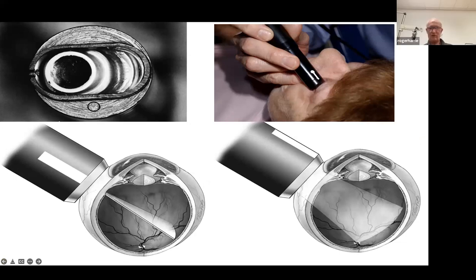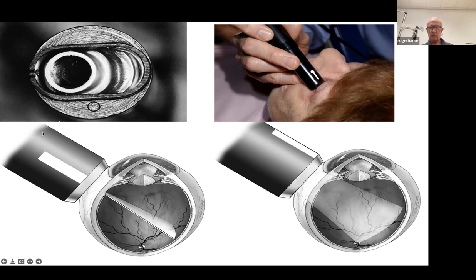This is a transducer here with the head removed, and this shows the actual transducer that generates the ultrasound. There's a little very thin ceramic crystal — microscopically thin — that's stimulated by electric pulses to vibrate and generate sound waves at very high frequency. Our standard B-scan probe is an 8 to 10 megahertz probe, and that generates the sound.